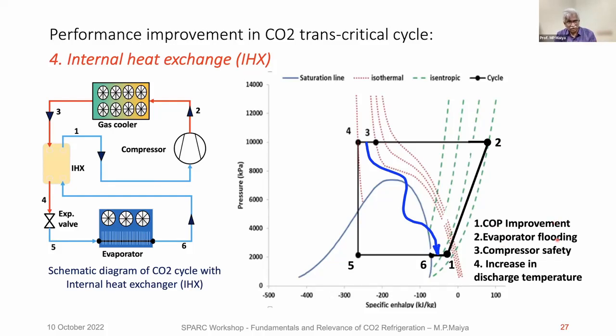Evaporator flooding is possible. By flooding the evaporator, you can have more efficiency for the evaporator and the whole system. Compressor safety: the compressor will never get liquid droplets, and the discharge temperature will increase. If you go this way, the higher discharge temperature is better for heat pumps or heating applications. So, 4 aspects of this. COP improvement may not be there always.